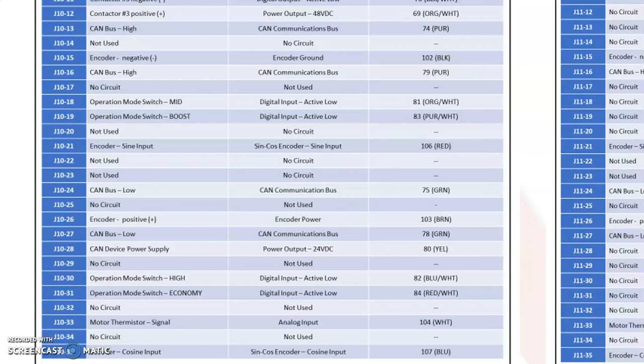18 is the mid-speed input. 19 is the boost speed input. 21 is the sine input from the encoder. So it's part of the speed signal. 24 is again the communication, the CAN. This is CAN low, and this is also the one that feeds the computer port and the motor controller. Pin 26 is power to the encoder for the generator. Pin 27 is the other communication line to the tachometer.